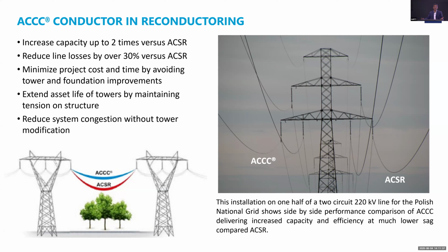If you need immediate power, the only way to get there quickly is reconductoring. This is what utilities have been doing for the last 40, 50 years when they need power quickly and have a problem with right-of-way or time. HTLS conductors can immediately give you two times the capacity of an ACSR conductor.